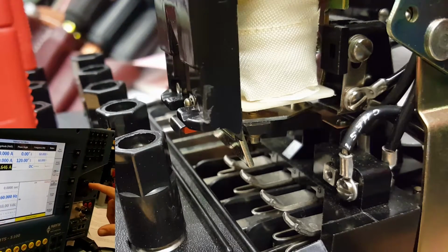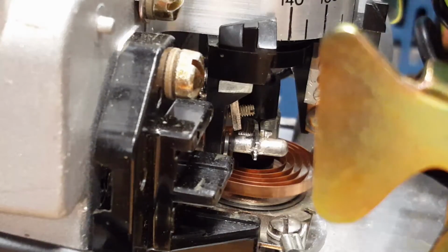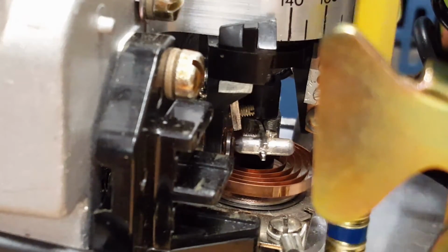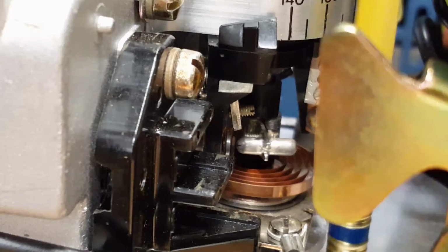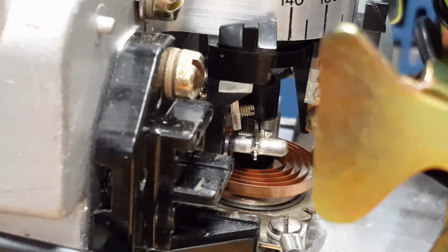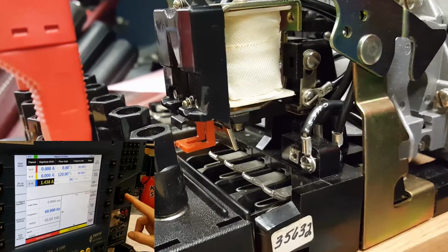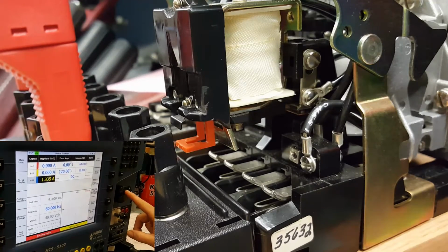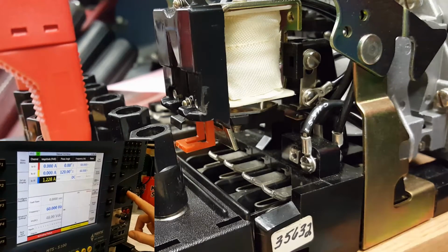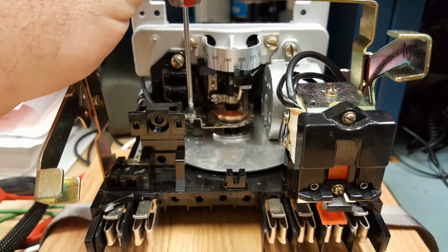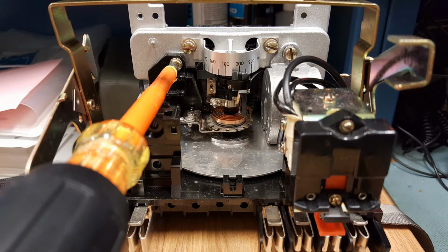I'll start at 50% tap value and ramp up until operation. I verify the seal-in by opening the low voltage circuit and also checking to make sure there's no arc. We will then ramp down the DC current to make sure that the seal-in drops out. This will complete our as found portion. Now we burnish our contacts, tighten any screws, and make any adjustments necessary before moving on to the as left.